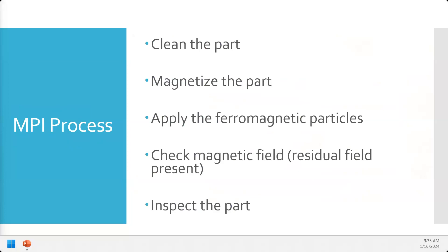After cleaning, we magnetize the part — most of the time using an electromagnet, which can be portable or fixed bench. Once magnetized, we apply the ferromagnetic particles and check our magnetic field to verify the part magnetized properly. These steps can be done in varying order — often applying particles while magnetizing, then checking the field and doing the inspection. Cleaning has to be at the beginning and inspecting the part at the end.